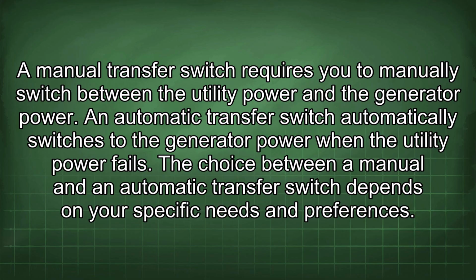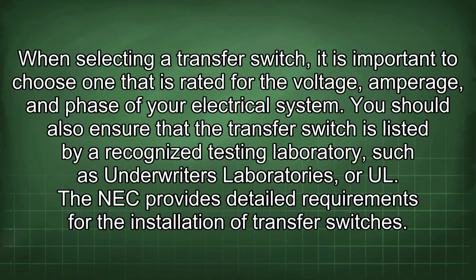An automatic transfer switch automatically switches to the generator power when the utility power fails. Choice between a manual and an automatic transfer switch depends on your specific needs and preferences. When selecting a transfer switch, it is important to choose one that is rated for the voltage, amperage, and phase of your electrical system. You should also ensure that the transfer switch is listed by a recognized testing laboratory such as Underwriters Laboratories, or UL.